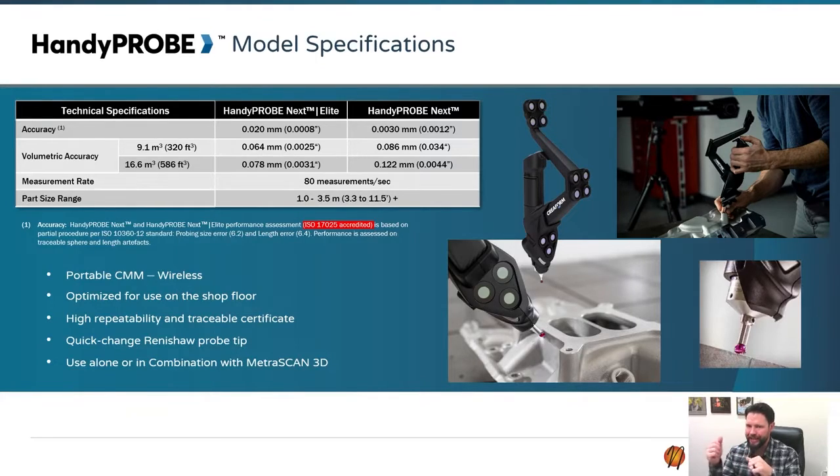The HandyProbe is the actual handheld CMM that pairs with the MetraSCAN. This is basically for when you want to take single points, probe some holes, or just don't need scan data and have pretty simple features. It's also much less expensive to just get the HandyProbe on its own, depending on your requirements.